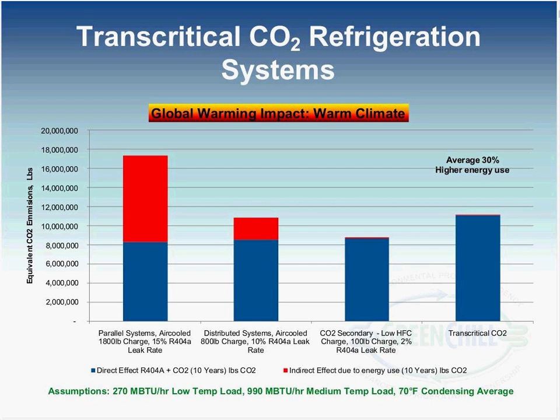And in most cases, it's when the system is operating in a lower pressure or subcritical state for the majority of the year versus in a transcritical region of the refrigerant. And in those cases, you can realize some energy improvement versus the energy consumption that the system has in a transcritical mode. So that's it, Keely. I'll turn it back over to you for questions.